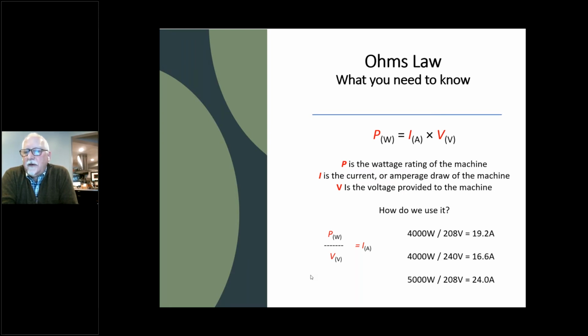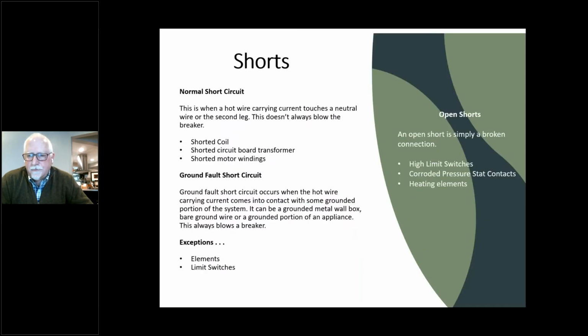And in the case of 5,000 watts at 208, that's 24 amps. That's going to have to sit on a 30 amp breaker. In some cases, if it was 240, it might just barely slide by on a 20 amp breaker. So Ohm's Law is a calculation that you use to figure out just exactly what you can get away with for new equipment in a building. Any questions?